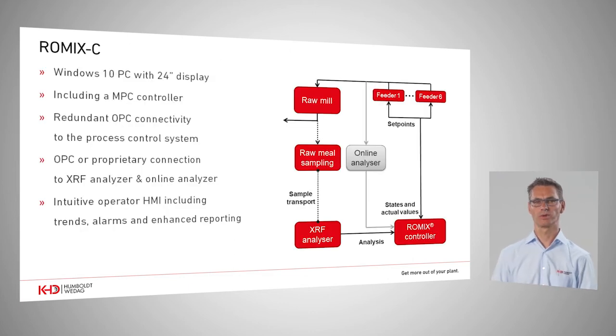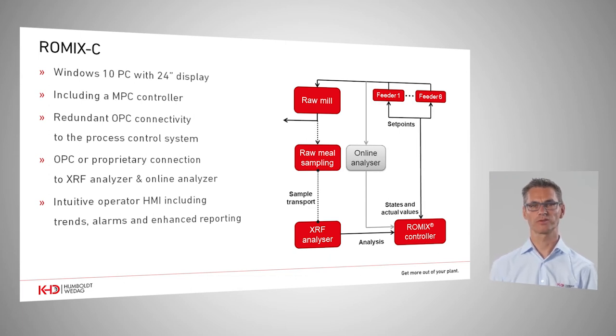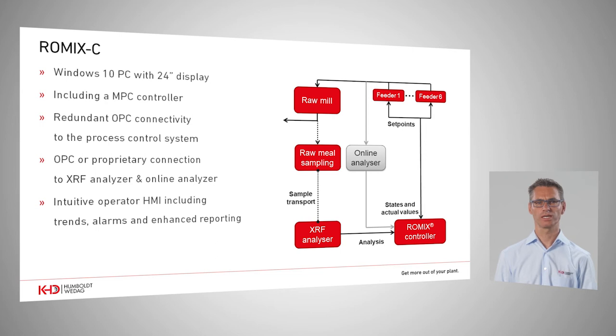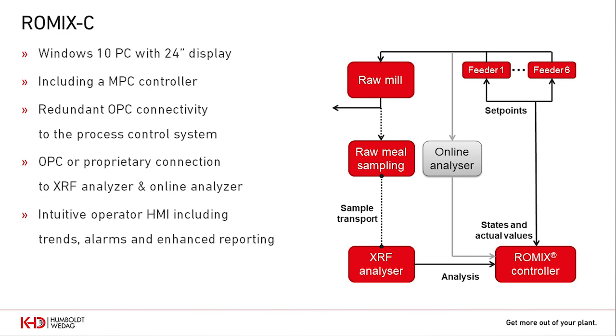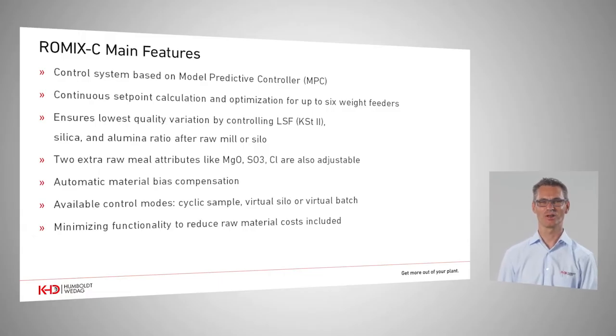Please have a look at the control diagram on the right. Let us start with raw mill sampling right after the raw mill. ROMIX-C collects the analyzer's values either from the lab or, if existing, from the online analyzer. Based on the results of the continuous analyzers, the MPC controller calculates and updates the raw mix set points. These are automatically forwarded to the various raw mill feeders. ROMIX-C can adjust up to six weight feeders simultaneously. ROMIX-C runs under a typical Windows machine and offers the MPC controller, the OPC connectivity to the process control system, and the data connection to the sampler, to the lab or to the online analyzer.